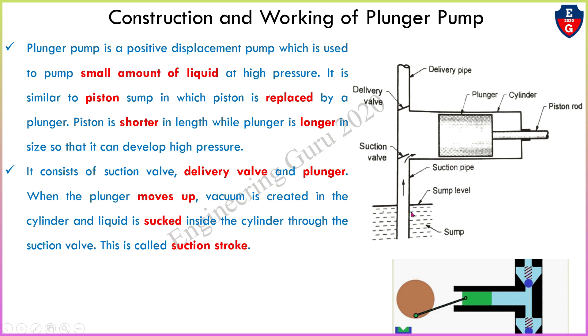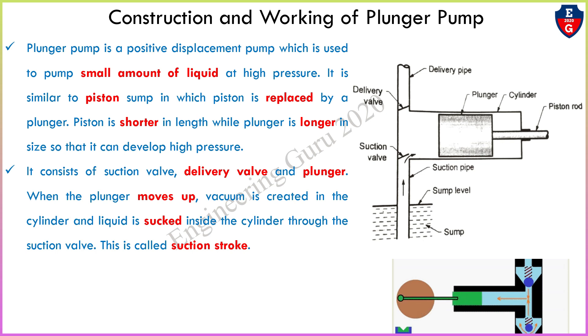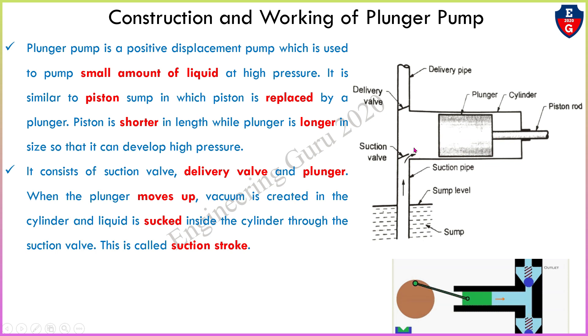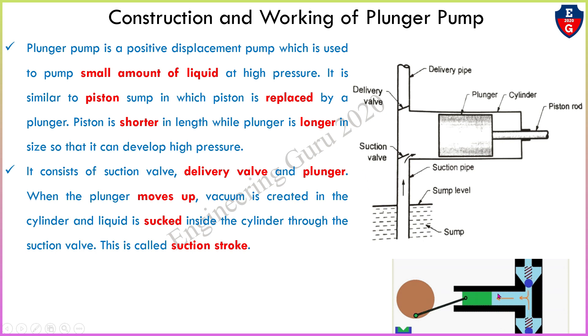Now understand the working of the plunger pump. It consists of a delivery valve. When the plunger moves in the forward direction, or we can say moves up, a vacuum is created inside the cylinder. The suction valve will open and water enters into the cylinder. When vacuum is created, the liquid is sucked inside the cylinder through the suction valve. This is called the suction stroke.